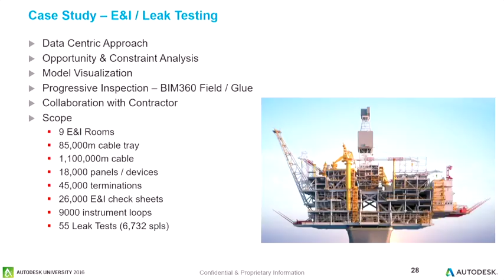We had 18,000 panels and devices, 45,000 terminations. Obviously each cable needs to be terminated at both ends; some were left coiled. There were 26,000 check sheets and 9,000 instrument loops from a static commissioning point of view, and then we ended up rolling this into leak testing.